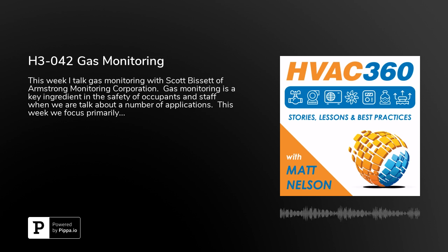Mm-hmm. When we're talking about solid-state sensors, it can be much worse, because a lot of those coatings can continue to off-gas for months, and that sensor oftentimes will not be able to tell the difference between an off-gas from floor sealant and carbon monoxide. I recall seeing an example of a condo building in Minnesota where they sealed the floor after installing solid-state sensors and effectively ran the heated garage all through the winter with 100% heat all the time. Wow! Because the sensors thought they were seeing gas all the time.